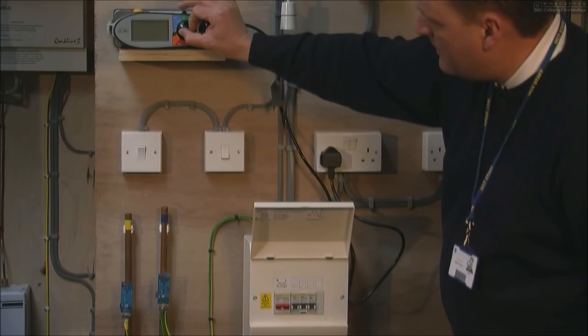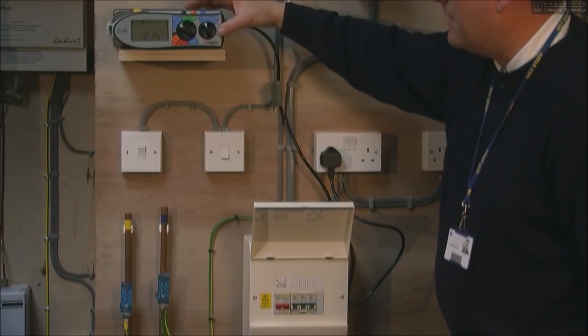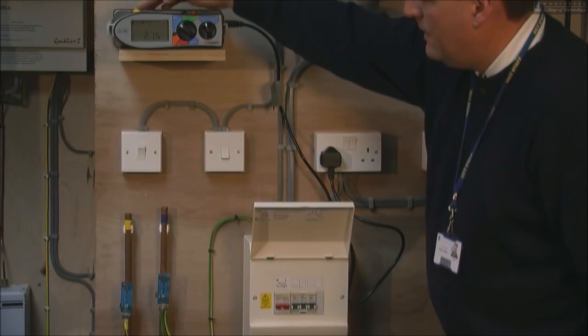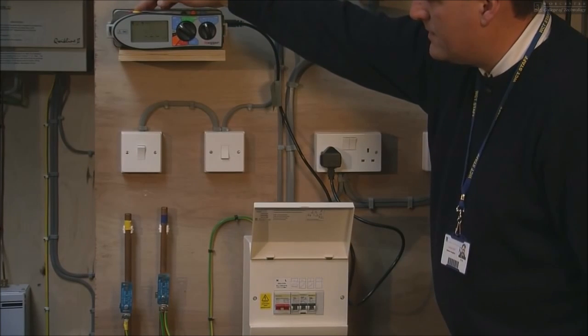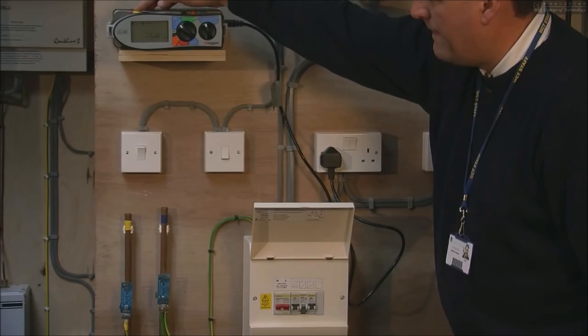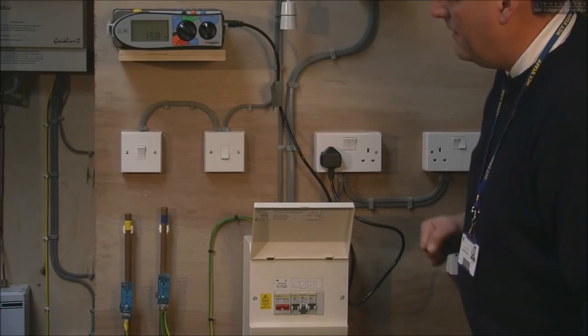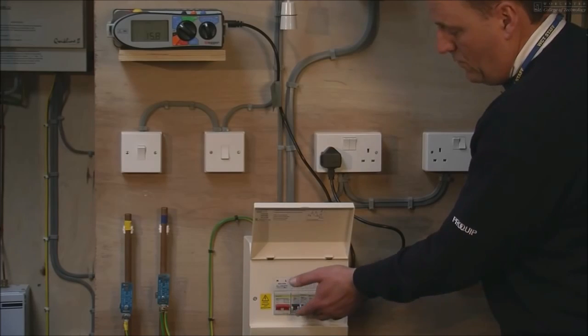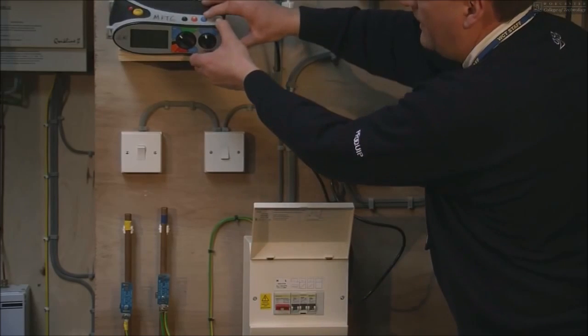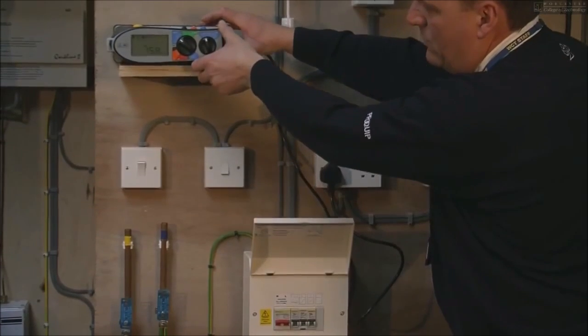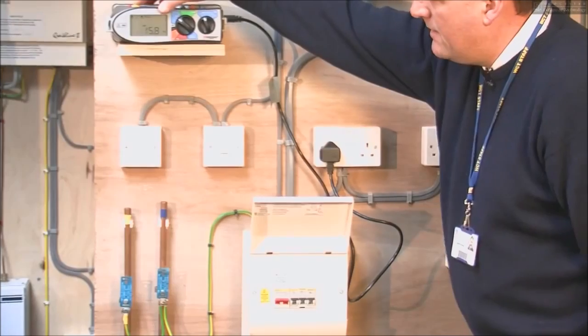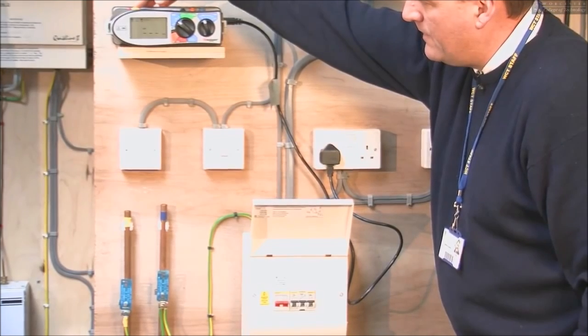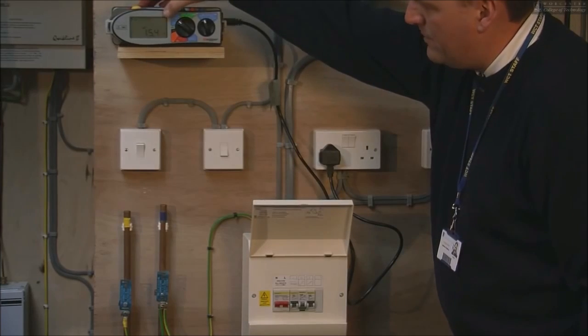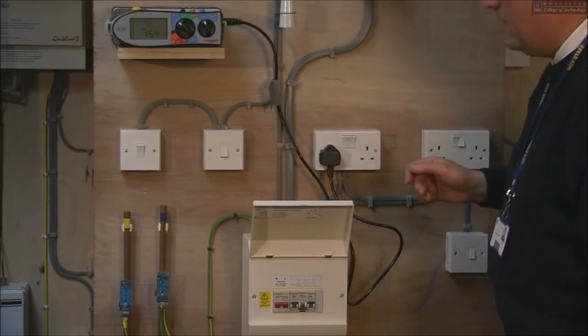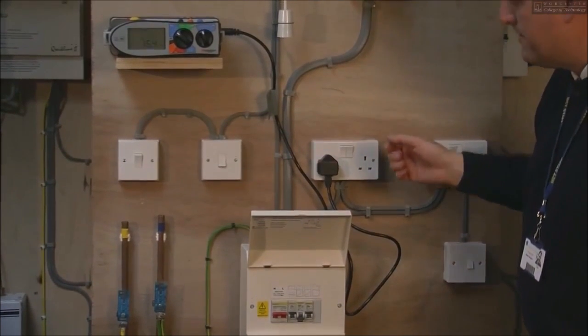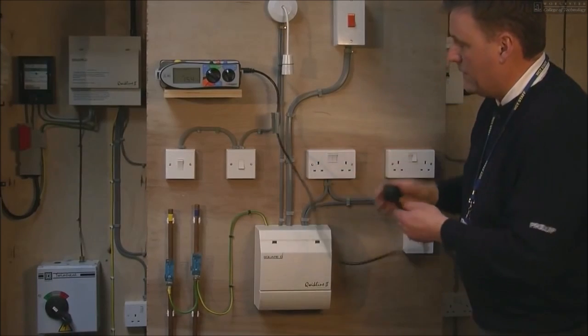We now set it to the ×5 test, so we're going to stick 150 milliamps through it now. Again, we press the test button. As you see, it's tripping at 15.8 milliseconds. Reset it. Again, back to 180 degrees. Press the test button. And we're tripping out at 15.4 milliseconds. And again, compare your readings to the relevant regulations. That concludes the RCD test.